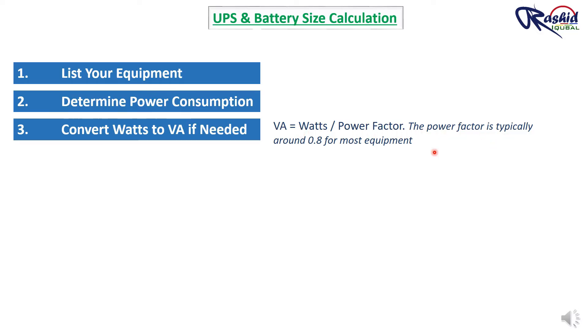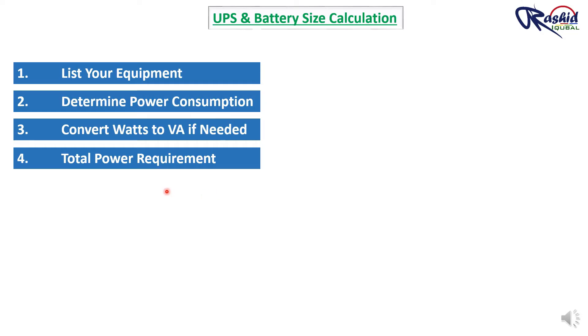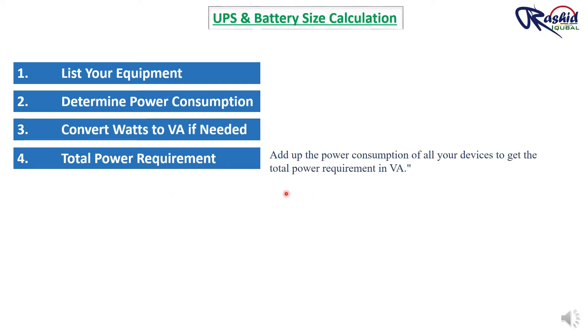Use the formula: VA equals Watts divided by power factor. The power factor is typically around 0.8 for most equipment, or you can select as per your requirement — it might be 0.9 or 0.85 depending on your design. Fourth, total power requirement: add up the power consumption of all your devices to get the total power requirement in VA.